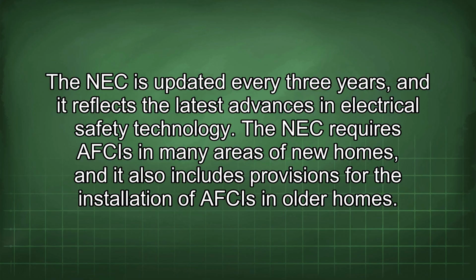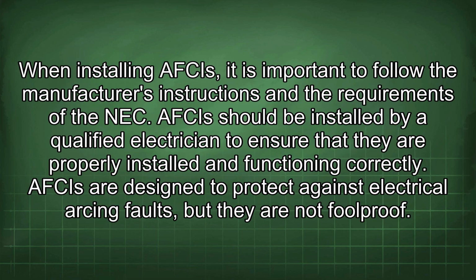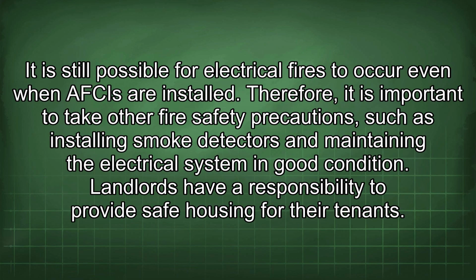The NEC requires AFCIs in many areas of new homes, and it also includes provisions for the installation of AFCIs in older homes. When installing AFCIs, it is important to follow the manufacturer's instructions and the requirements of the NEC. AFCIs should be installed by a qualified electrician to ensure that they are properly installed and functioning correctly. AFCIs are designed to protect against electrical arcing faults, but they are not foolproof. It is still possible for electrical fires to occur even where AFCIs are installed. Therefore, it is important to take other fire safety precautions such as installing smoke detectors and maintaining the electrical system in good condition.